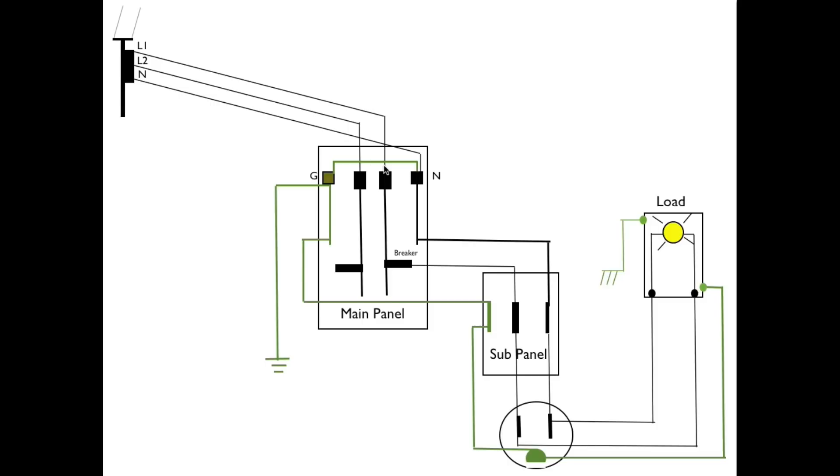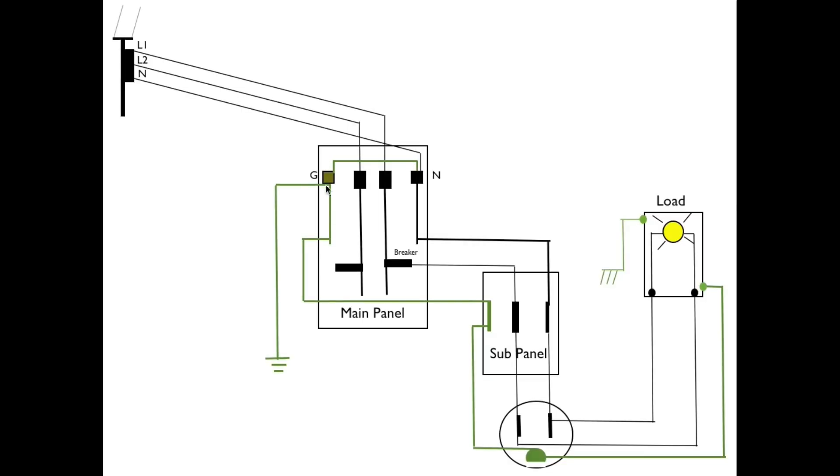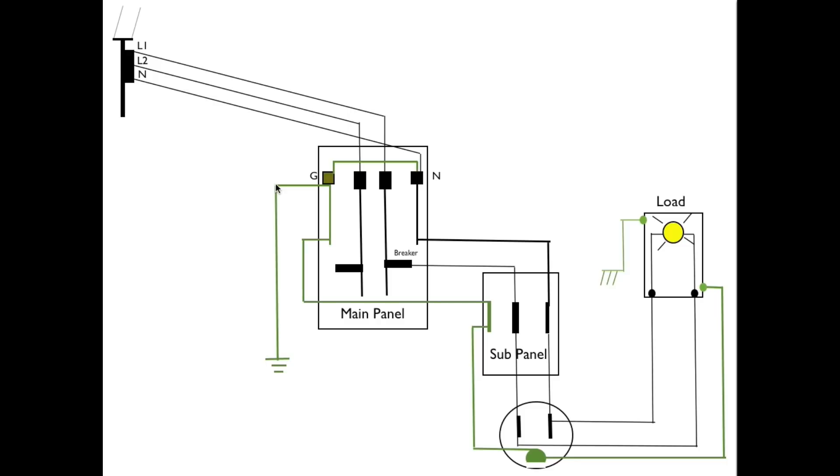Okay when it comes into the main panel. Now this is a main panel here. There is a connection between the neutral on the pole and the neutral bar in the panel. There is also a jumper that goes from neutral to ground. Now this is ground here and this is earth ground. And of course it has a bar also.